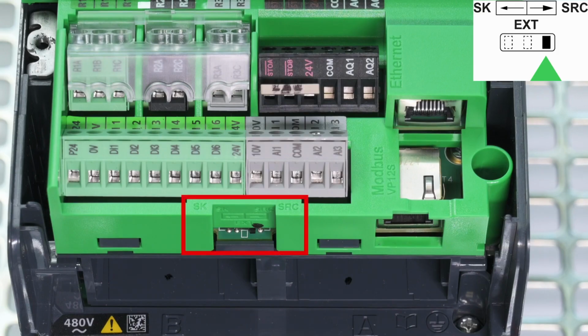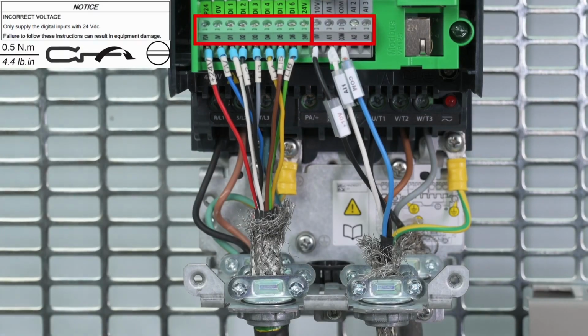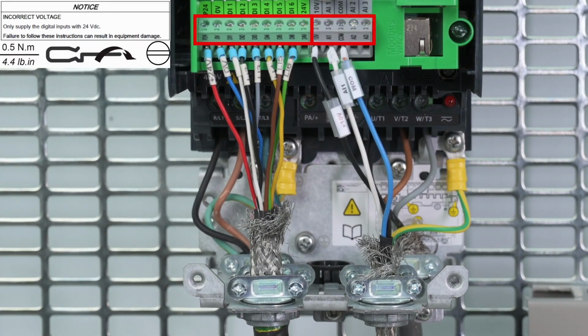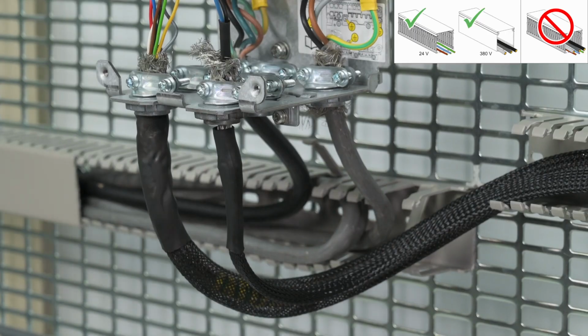Verify that the switch is on default position SRC mode. On the control part, we perform the same operation with both potentiometer for speed reference and DI for run order. To improve electromagnetic compatibility, please use shielded cables for analogic and digital parts and keep them separate. Keep the power and the control cables separate to improve the electromagnetic compatibility.